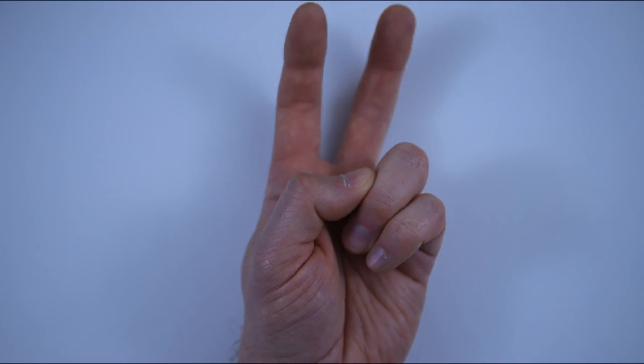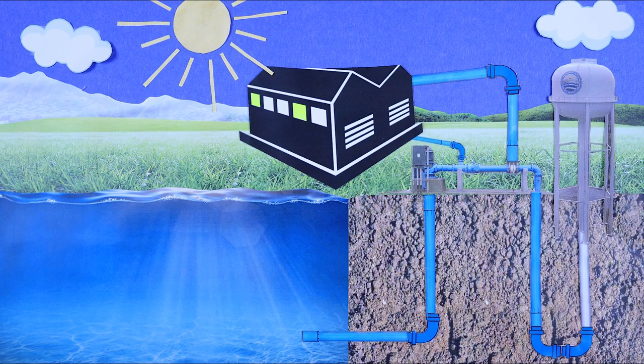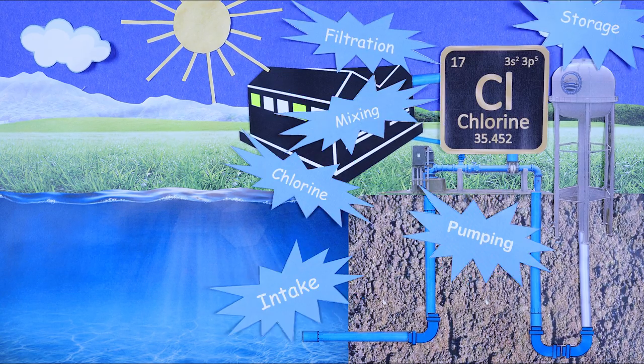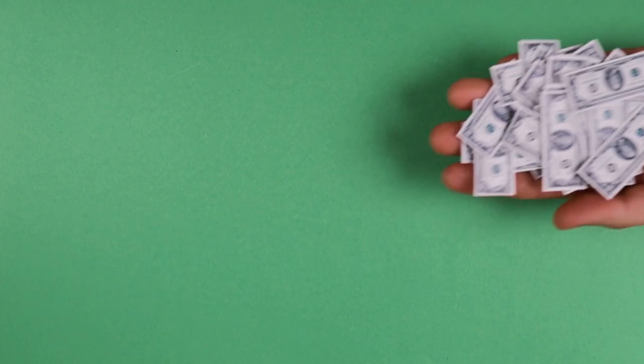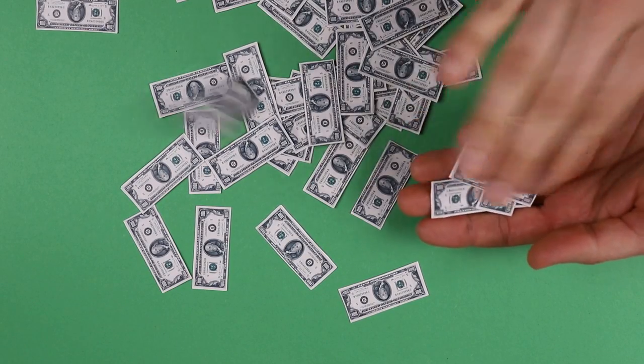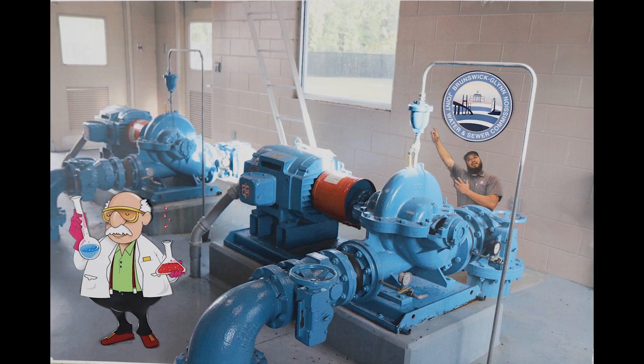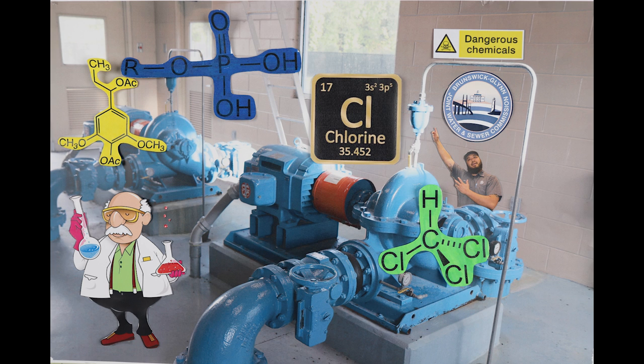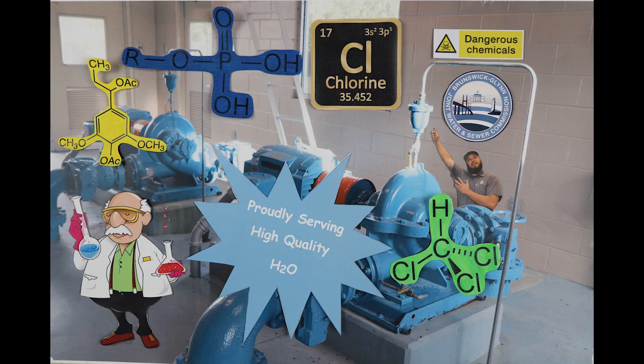There are primarily two types of water systems: surface water and groundwater. Surface water systems tend to be more costly due to a myriad of steps needed to filter, disinfect, and treat the river, pond, lake, or rain runoff water. All of our water is sourced from wells, much like local small community or single residential use wells. We are able to keep costs down using this type of system due to the minimal treatment required, thanks to the naturally high quality of local groundwater. Our water production operators typically do no more than test the water for mineral level, shock it with chlorine at a safe level to inhibit bacterial growth during periods of reduced flow in the pipes, and then add a small amount of phosphates for corrosion control in the galvanized pipes.